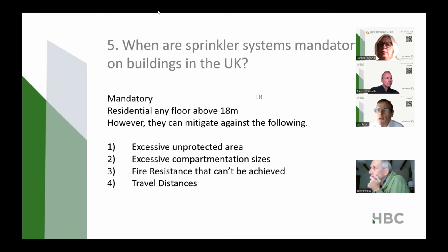So they're mandatory in Wales. They're not mandatory here at the moment, as far as I'm aware. Certainly the last two care homes, but what they also do, they're a lot more resilient because they go up to a category 3. So there's more resilience in the sprinkler system as well, more resilience in the water supply, and more resilience in the protection of the power supply too. So, I would imagine that whatever's the case in Wales, it'll probably follow to the UK.